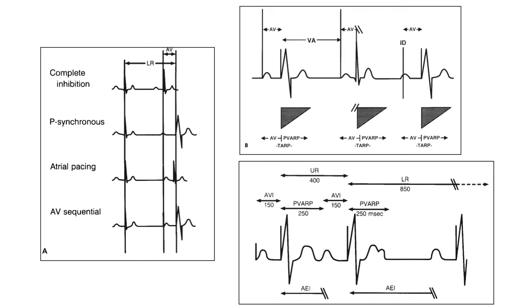And there are four variations of the DDD timing cycles. The first one, here in figure A in the first panel: if intrinsic atrial activity occurs before the termination or the end of the lower rate limit, both channels will be inhibited and no pacing will occur. But if a P wave is sensed before the end of the ventriculoatrial interval, the output from the atrial channel will be inhibited and an atrioventricular interval will be initiated. If there is no ventricular activity sensed before the termination of the atrioventricular interval, a ventricular pacing artifact will be delivered, and this is called P-synchronous pacing, here in the second panel.